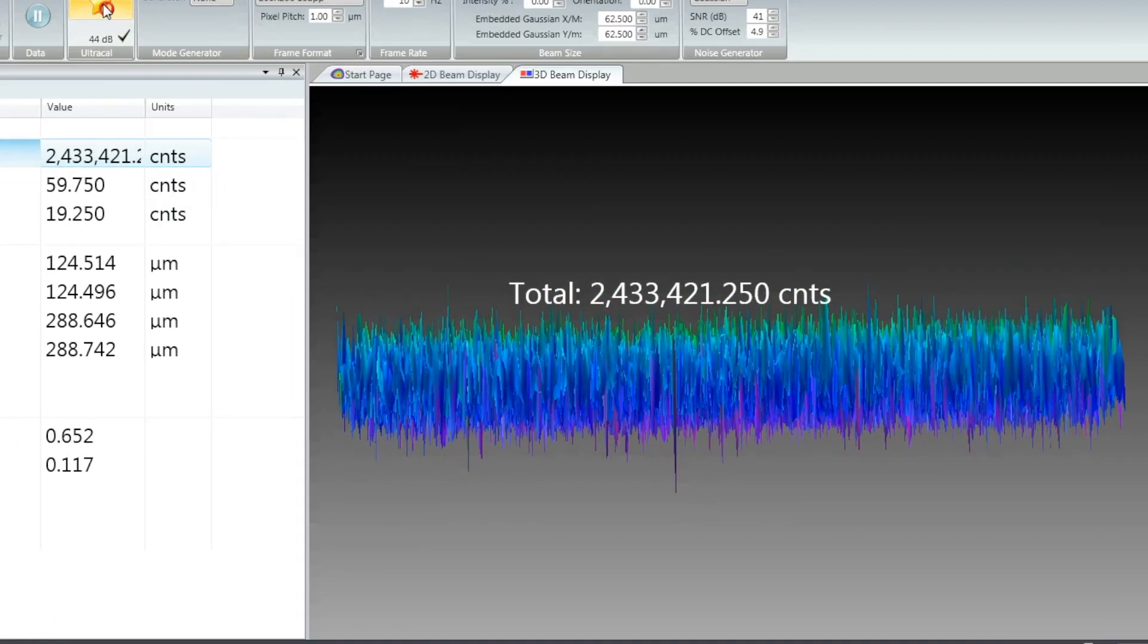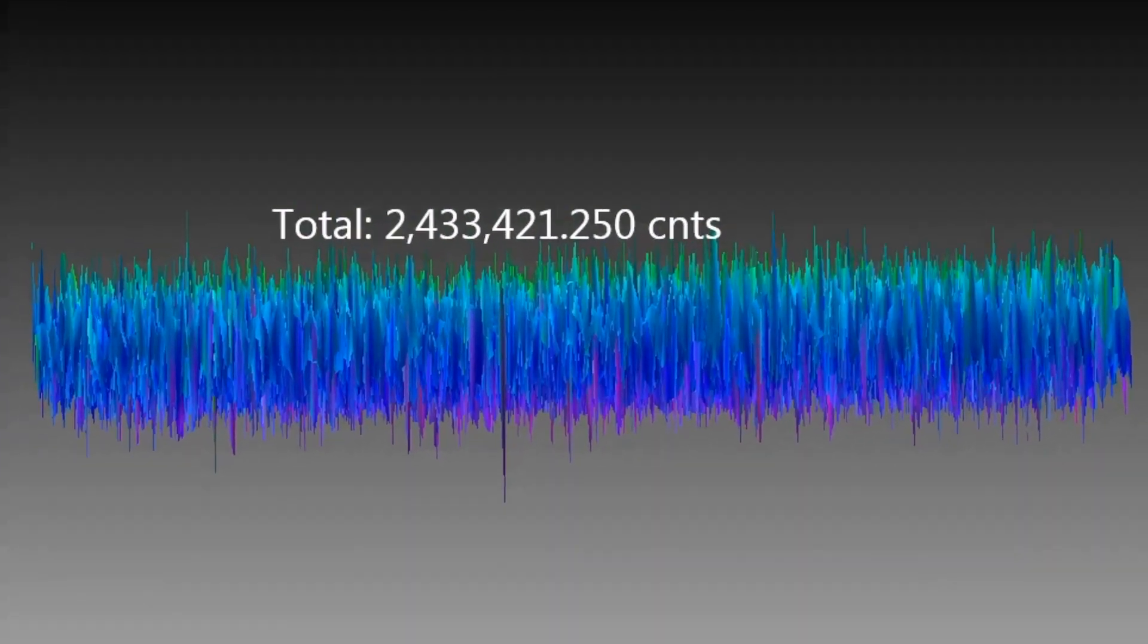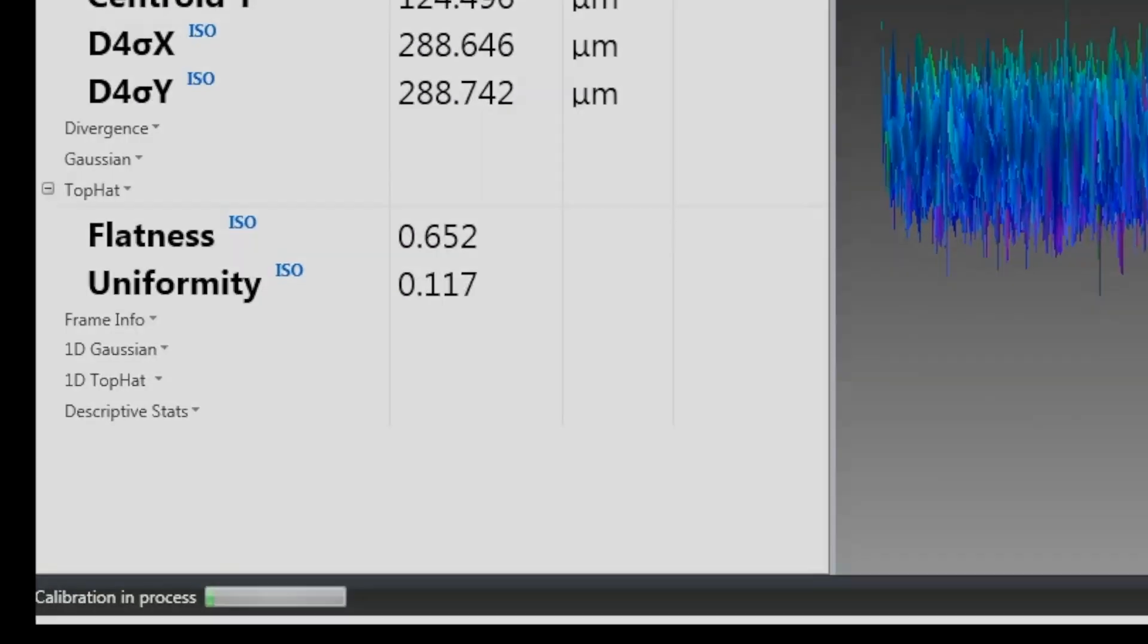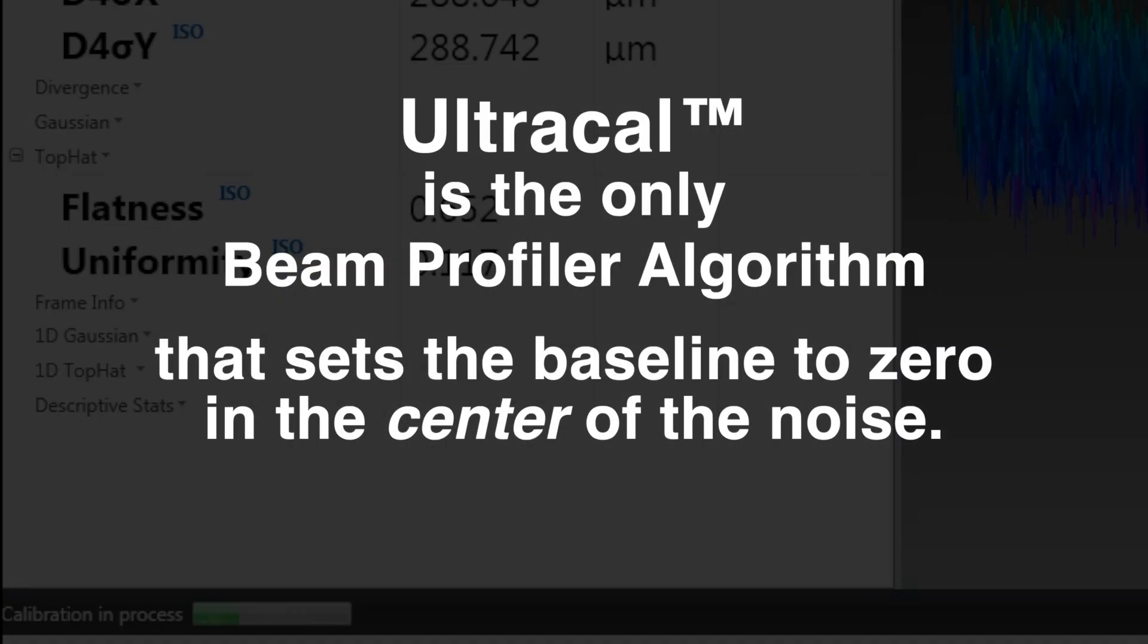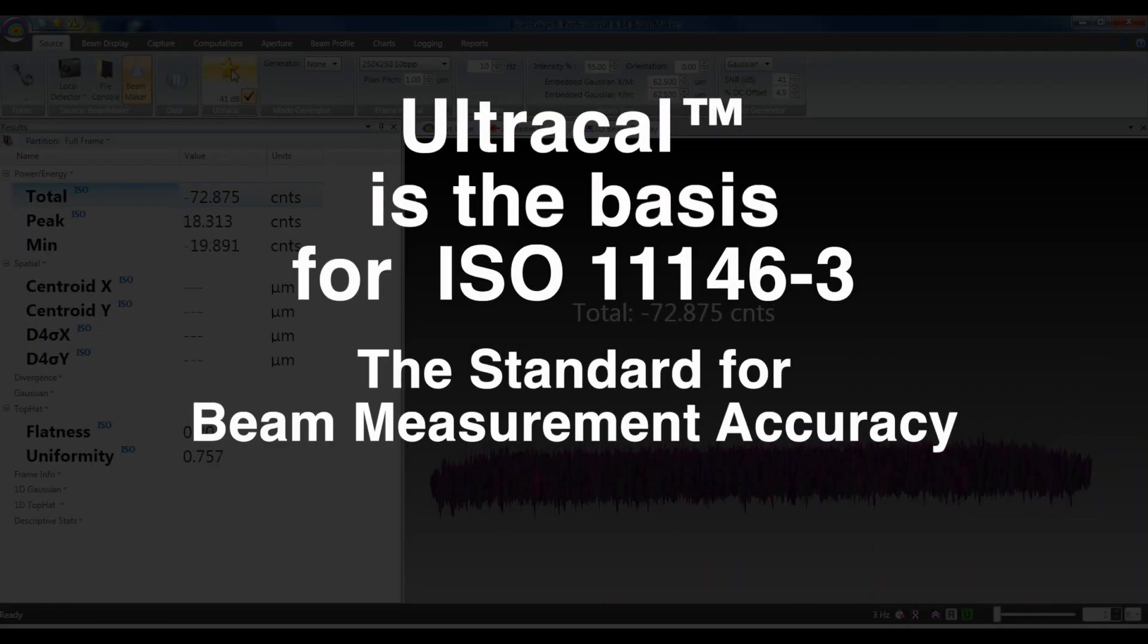Other beam profiling products use less sophisticated algorithms that perform a baseline subtraction, but truncate the noise below the zero of the baseline. This leaves only a positive component, which adds a net value to all beam measurements. UltraCal is the only beam profiler algorithm that sets the baseline to zero and in the center of the noise. It is no surprise that Spiricon's UltraCal helped establish the ISO 11146-3 standard for beam measurement accuracy.